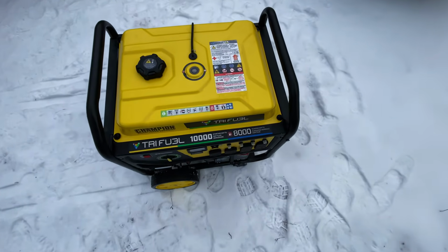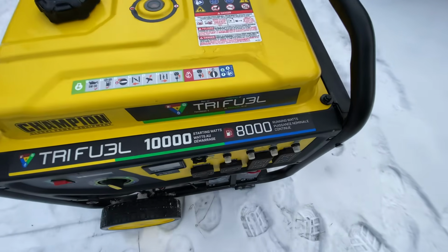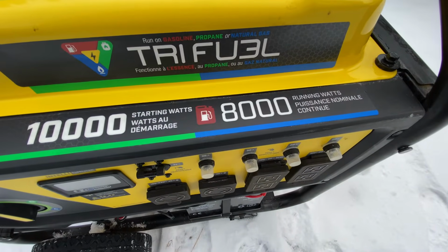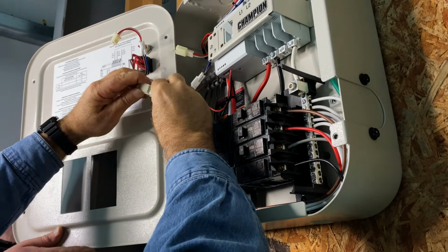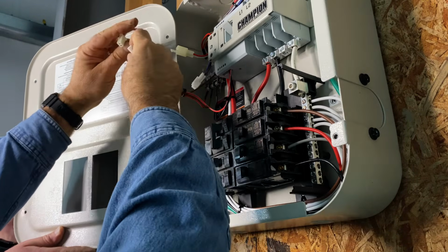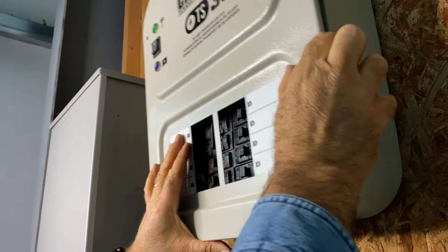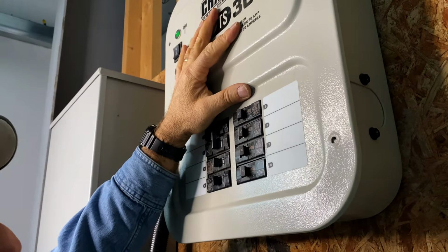electrical panel. Now, it's important to understand that portable generators don't typically put out enough power to energize everything in most homes, so one way or the other, you'll need to choose which circuits to power. Installing a transfer switch just means you make this decision ahead of time, as circuits are rerouted into the manual transfer switch panel during installation.